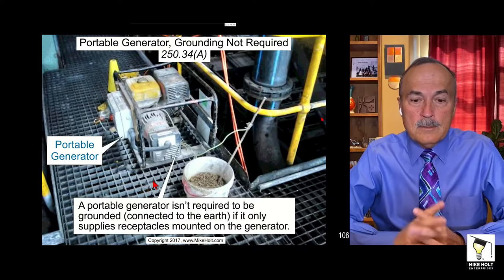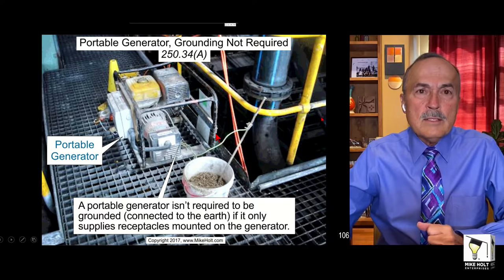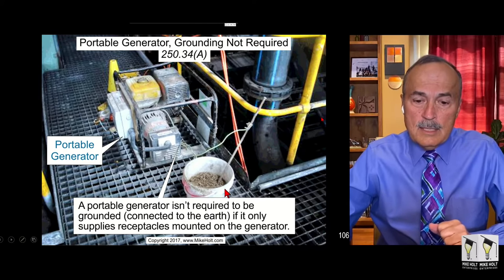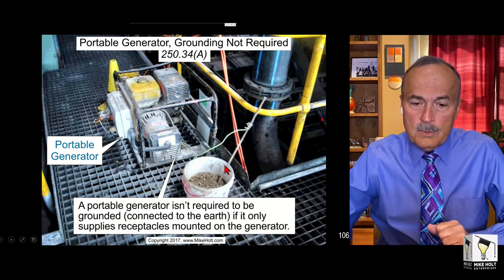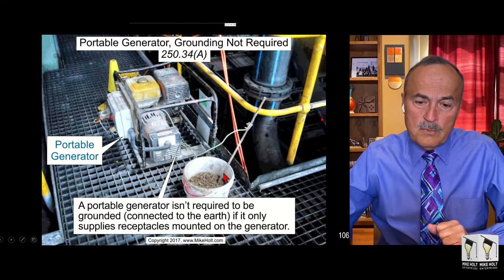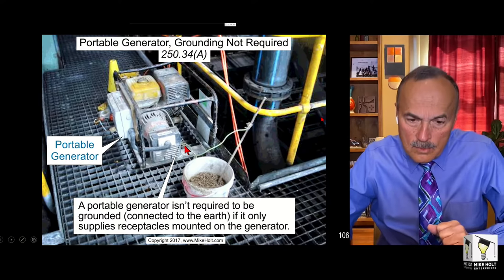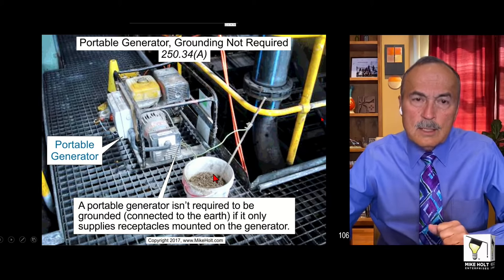Eric Stromberg gave me this one - here's a portable generator. Somebody thinks you've got to ground the generator, so they take a five-gallon bucket, put some dirt in there, get a three or four-foot piece of ground rod with a wire, and connect it somewhere to the frame of the generator.